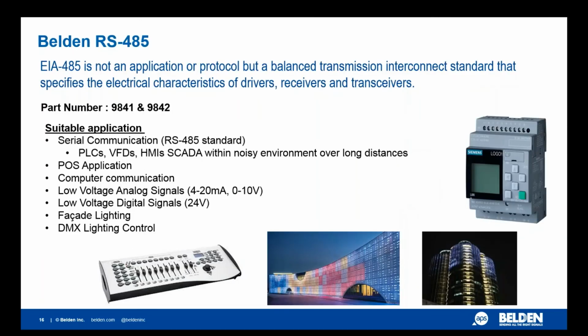So Belden RS-485 or EIA-485, it is not an application or protocol, but it's a balanced transmission interconnect standard that specifies the electrical characteristics of drivers, receivers, and transceivers. So commonly known in the market is a Belden 9841 and 9842. They're a suitable application for the RS-485 standard. They're used across the different applications of point of sale applications, computer communications, analog signals, digital signals. You can utilize it in facade lighting and also in a DMX lighting control system if required.